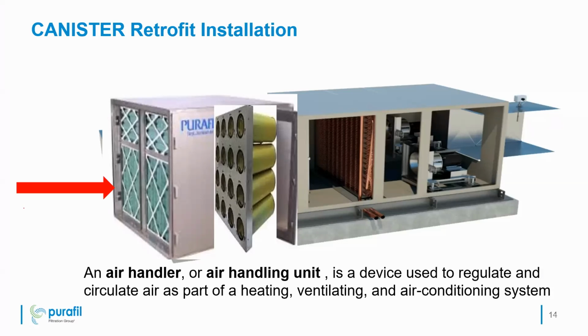This complete system works on recirculation because we are here to clean the bacteria and virus from the indoor. So it will not be helpful for pressurization? You can use it, but we are recommending recirculation because human occupancy is inside. The bacteria and virus are not coming from outside. It depends on the application. If you talk about bacteria and virus, I would recommend recirculation. If you talk about contamination from outside, I will say pressurization. Okay.